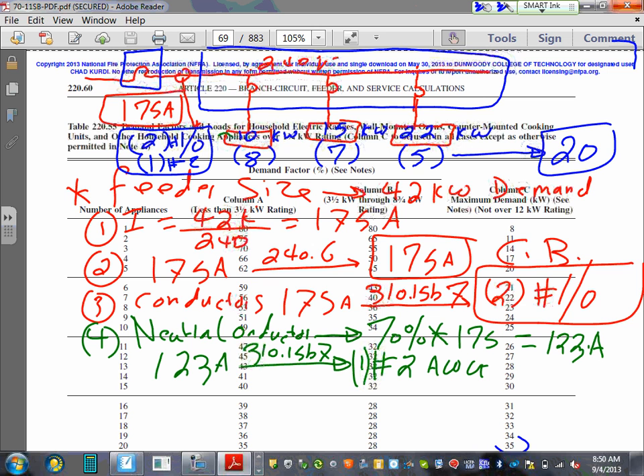So I size the feeders. I need to go size the branch circuits now. I'm done with the feeders. Feeder sizing, we did the demand and we sized it. Okay. Now let's pipe it. Let's size the pipe. I'm going to use my calculator for that one, and you guys will do the math on that. Let's go size the pipe, because that's typically what we do. We really end up with a pipe.